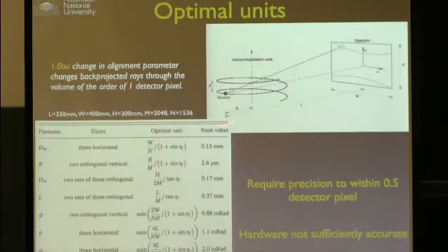So that's not a distance we can measure physically. More to the point, it's a distance that can change over time. It changes as the filament in the source gets older, so this is hopeless to measure. The other ones are sort of okay, not too bad, but this is the really difficult one. I can mention that if we start with the X-ray source cold, turn it on, that distance changes by at least 40 microns.